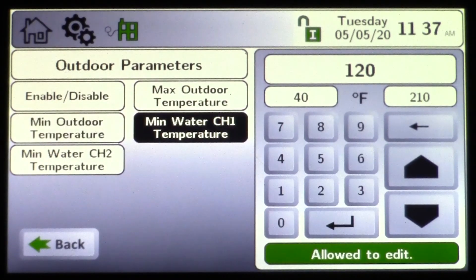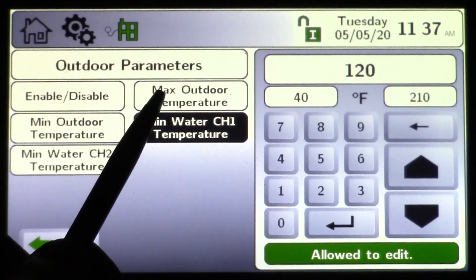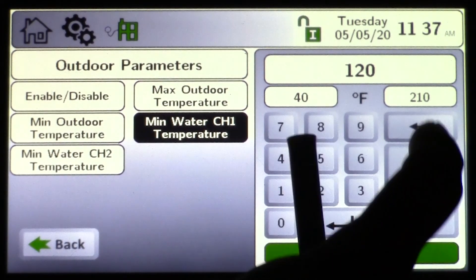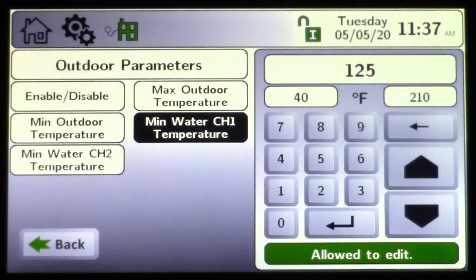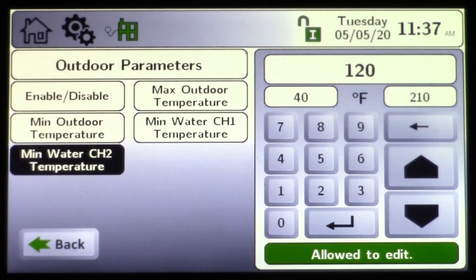Minimum water temperature is the minimum temperature you need to supply to the heating system on a warm day. On a 50-degree day, maybe that's 100, 120, or 130 degrees — get in and make your changes and click OK. If you were utilizing CH2, you could come in and choose that minimum water temperature as well.